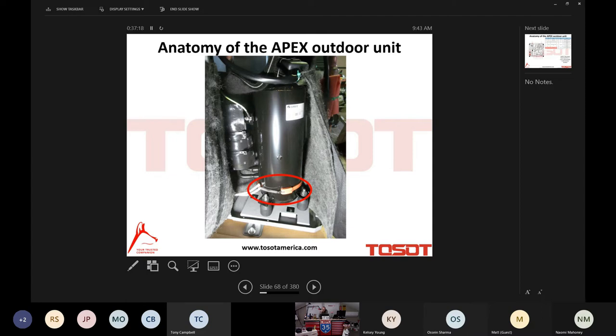Now, I know you're all sitting there, I can't see you, but I know every one of you just sat back and said, "What the heck is that? Who's going to wait 8 hours to commission the system?" Well, we'll talk about it. We can lessen that time. It all depends upon the outdoor air temperature. It also depends upon whether the unit has been stored in a heated or somewhat climate-controlled warehouse, like an Emco, which is all good news. But the key to this is to encourage our installers: the first thing they should do at a job site is to set the outdoor unit and bring power to it, and then do everything else. We'll talk about this kind of wacky 8-hour preheat requirement and how we can cut that down quite a bit and make it a little more reasonable. So we'll talk about that as we move forward.